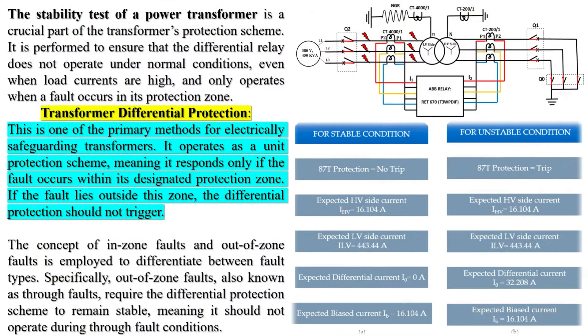The stability test of a power transformer is a crucial part of the transformer's protection scheme. It is performed to ensure that the differential relay does not operate under normal conditions, even when load currents are high, and only operates when a fault occurs in its protection zone.